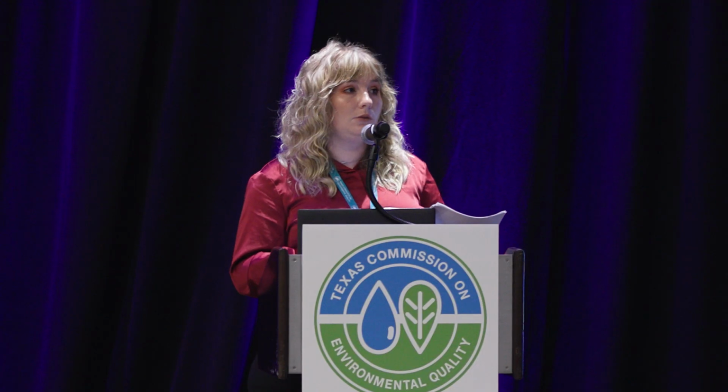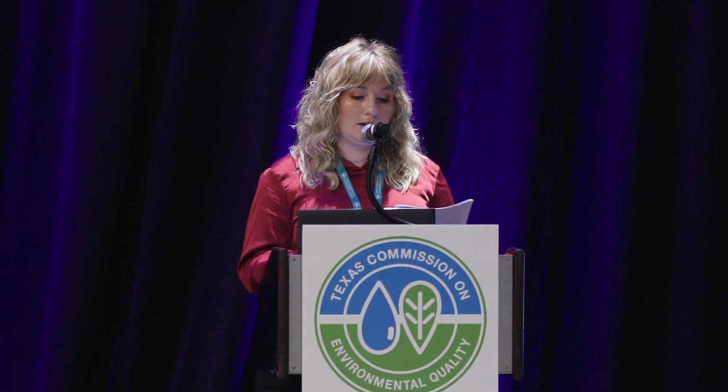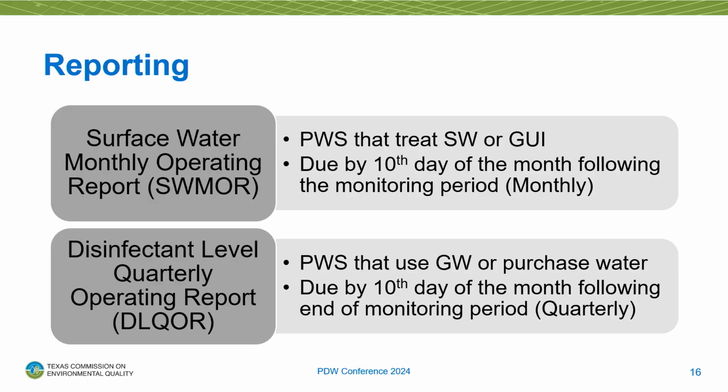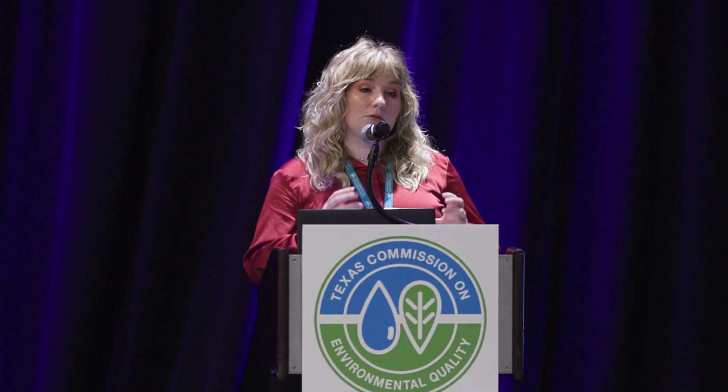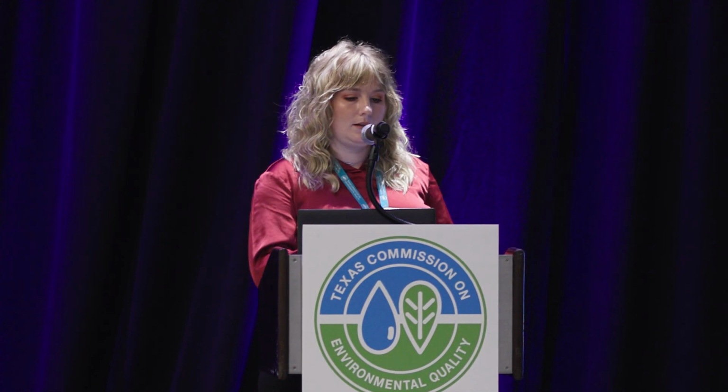So your January report is going to be due February 10th, February report, March 10th, and so on. For systems using groundwater or purchased water, we have the DLQOR, or Disinfectant Level Quarterly Operating Report. This is due on the 10th day of the month following the monitoring period, which is quarterly. That means first quarter is January through March, so you're going to turn that in April 10th. Second quarter is April through June, so you're going to turn that in July 10th, and then so on.